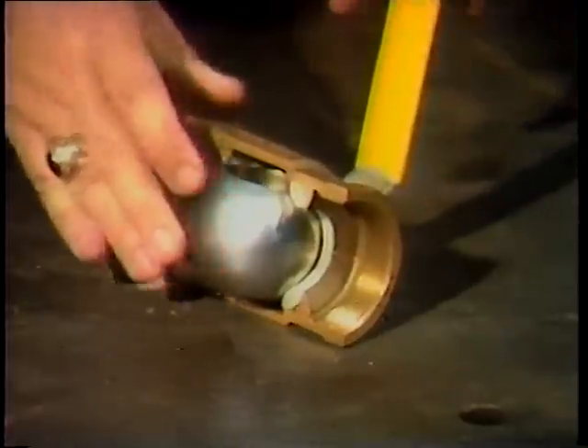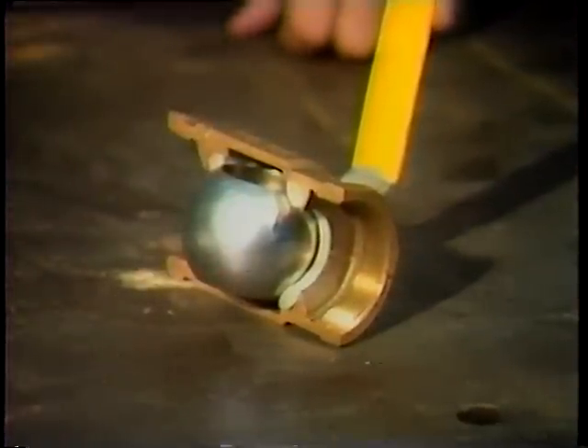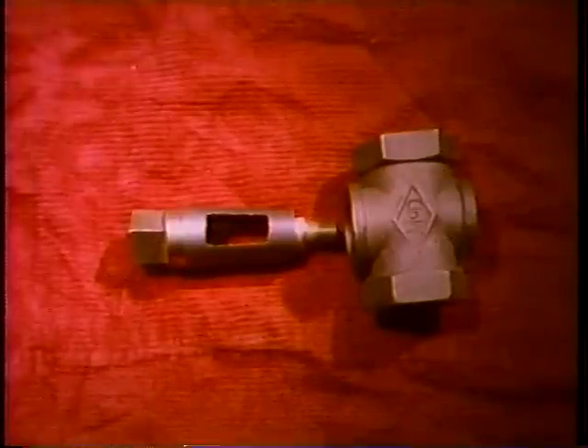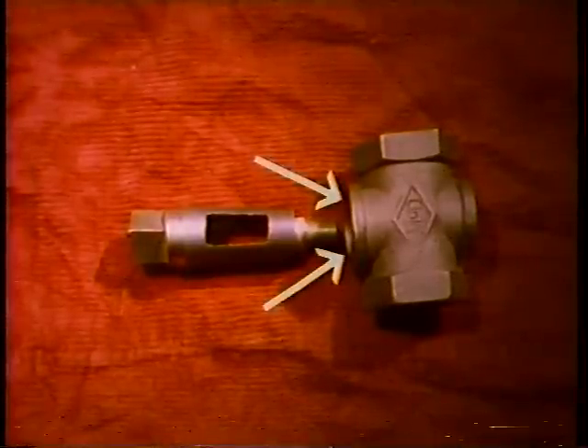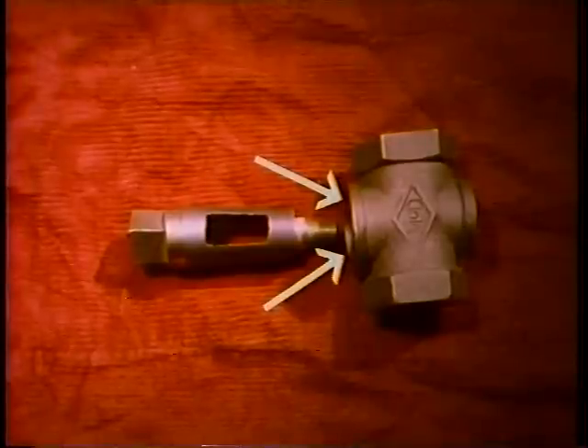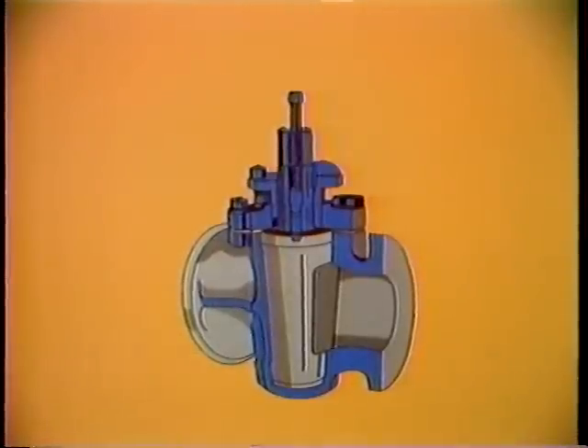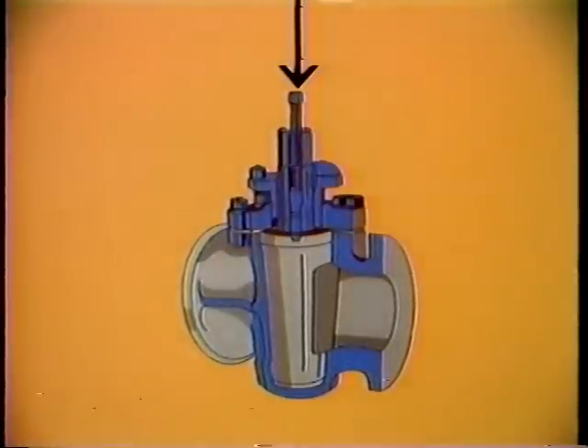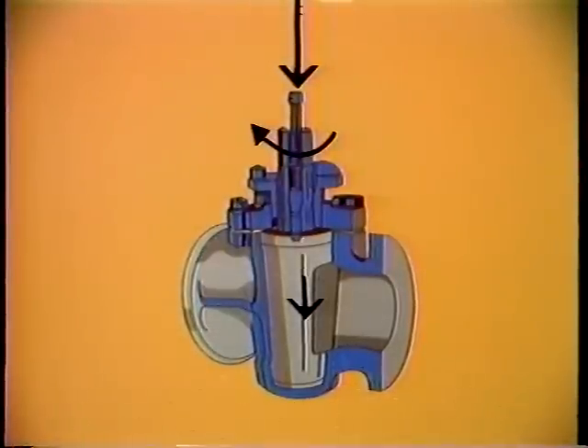The seals can be damaged by this pressure and repair work would be needed. The seats on the plug valve are usually built into the body. Many plug valves are equipped with plastic-coated self-lubricating seats; the others must be manually lubricated — this one works just like a cup lubricator for a bearing. A lubricant screw attached to the top or bottom of the valve is rotated, and lubricant is forced into grooves at a higher pressure than the system pressure. This keeps any solid particles in the system flow from getting lodged between the plug and valve body.